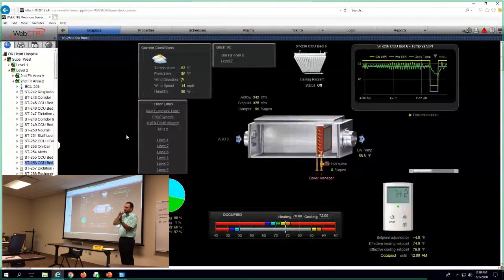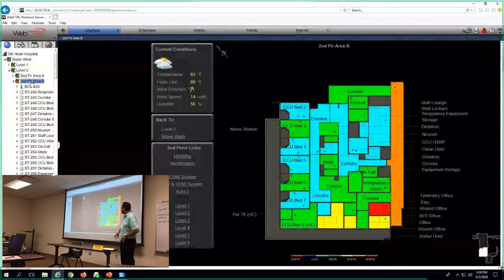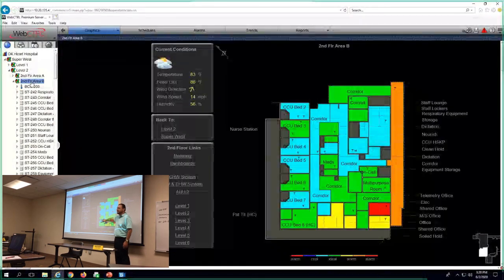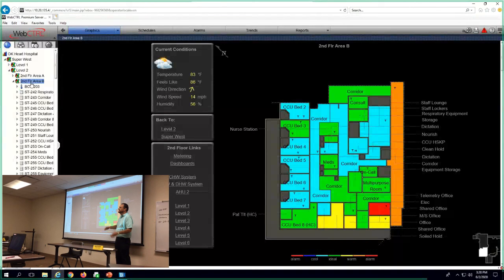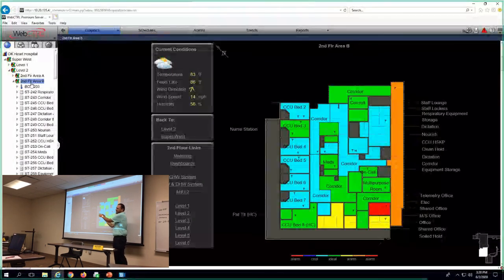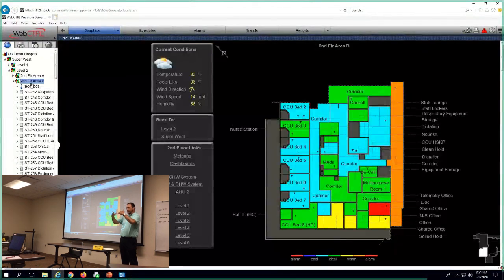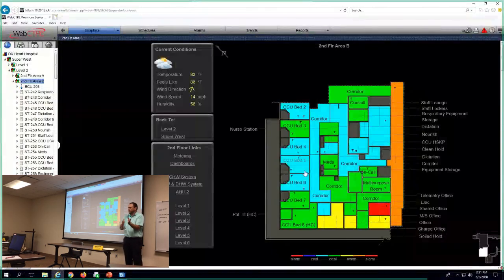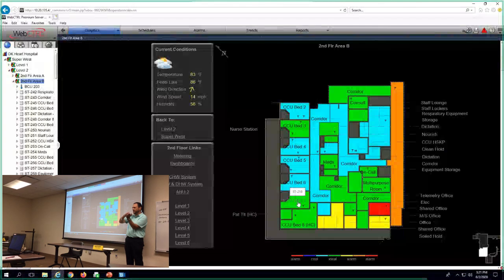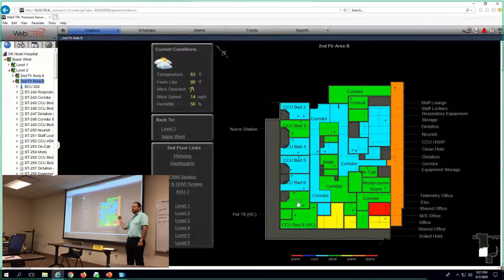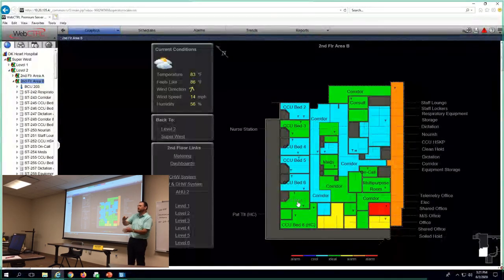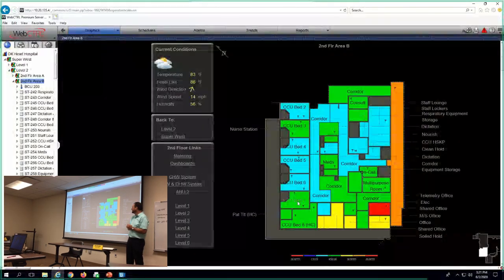Because the reason is, if you back up to that floor plan, Joe, if this zone and this zone are not somewhat close, you will always be fighting each other. This zone and this zone are both in the corridor. These two VAVs will sit there and fight each other all the time, because one set point's up, one set point's way down. One person is running theirs up to 85, one's running it down to 55, and the next thing you know, it becomes an energy hog, and you're fighting each other all the time. But if we can keep people satisfied and within an acceptable parameter, then it's win-win for everybody, because it's going to be a lot more energy efficient. You don't have this zone trying to overcome the cooling of this zone, or this one trying to overheat the zone that's calling for cooling, and we can maintain reasonable parameters. So jump back in there, Joe.